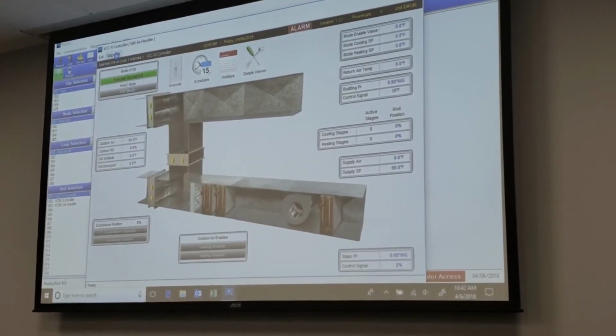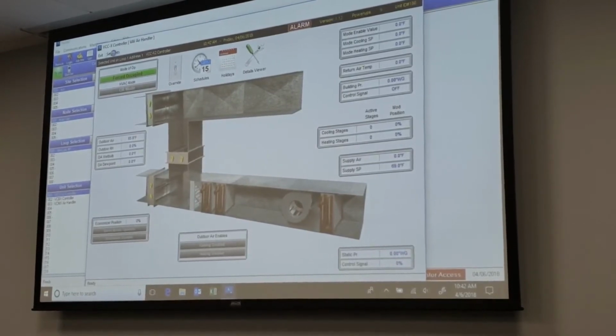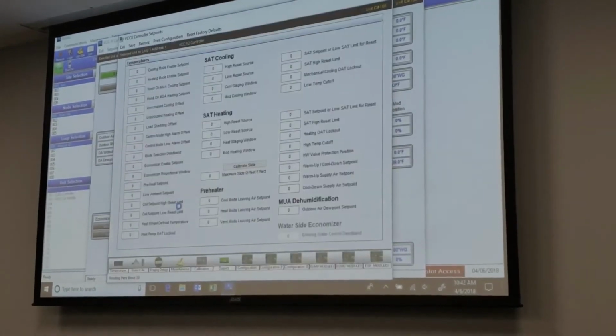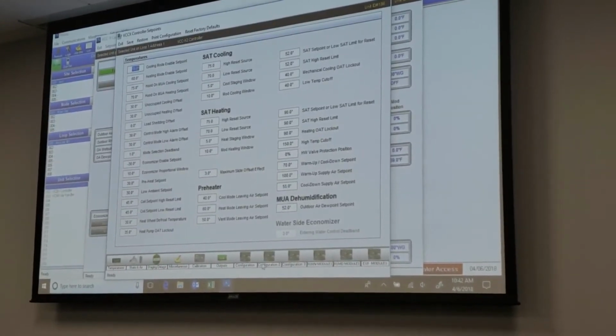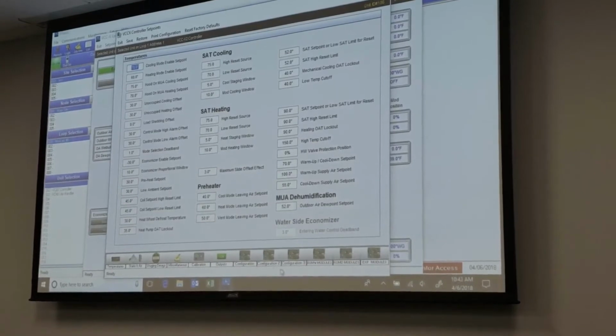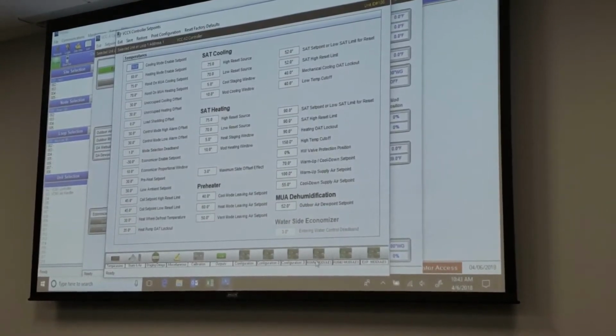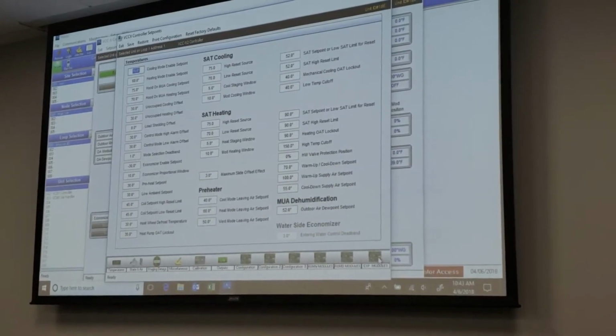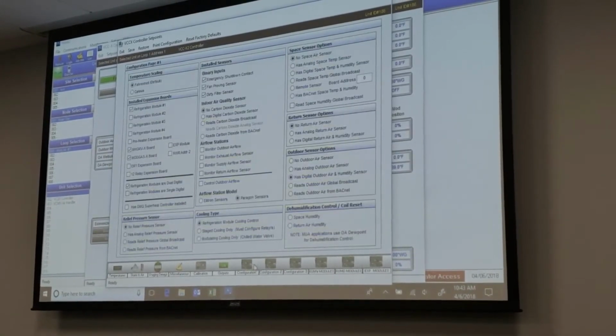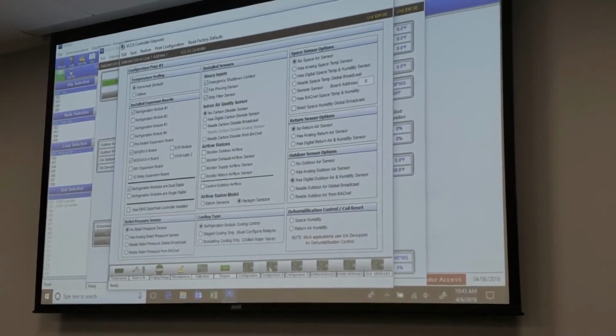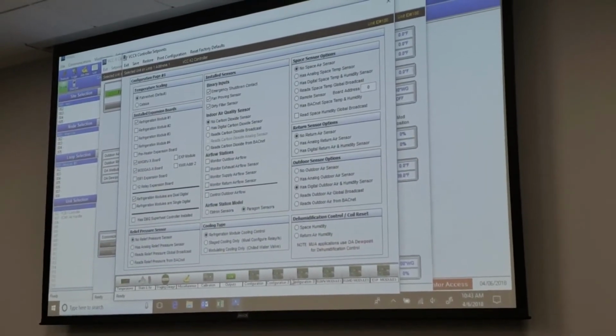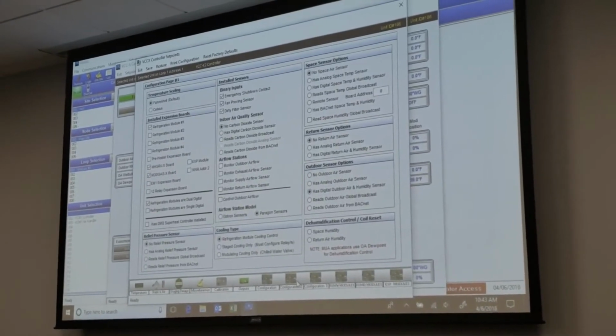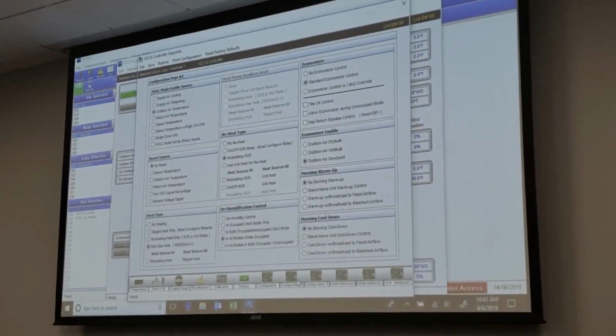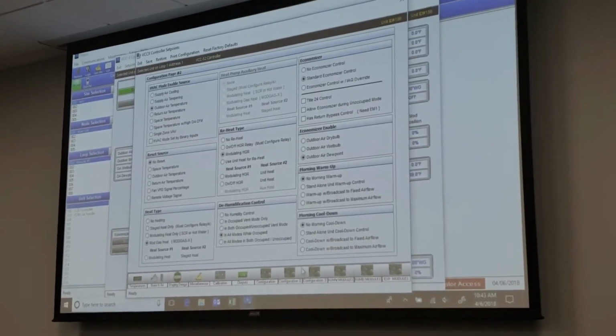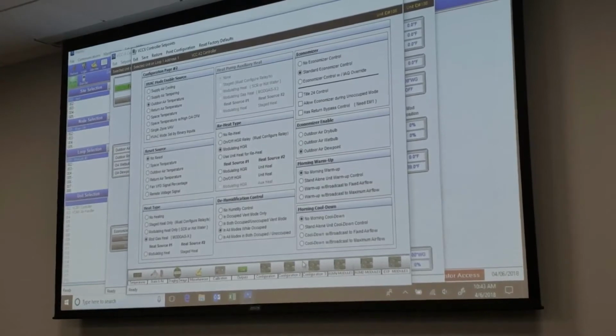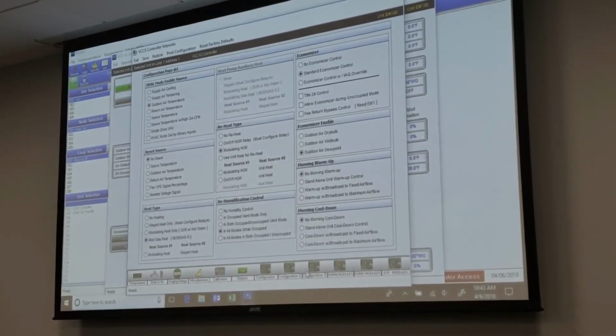now this guy has a whole bunch of configuration. This guy's got configuration screens 1, 2, 3. You've got refrigeration modules. You've got an RSMV, RSMD, and then expansion boards. So these guys do a lot more. The capability of the VCCX2 is a lot more. You can actually control VFD driven compressors. You can also control the digital compressors. You can control the superheat. Electronic expansion valves is what they're equipped with, or most of them are equipped with.